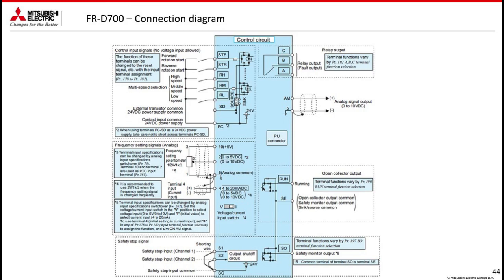Finally, there are the open collector transistor outputs. SE is the open collector reference potential. So I will bring a positive 24 volt. Run is the output which will provide me with a positive signal when the motor has exceeded 0.5 Hz, and SO when the safety has intervened.